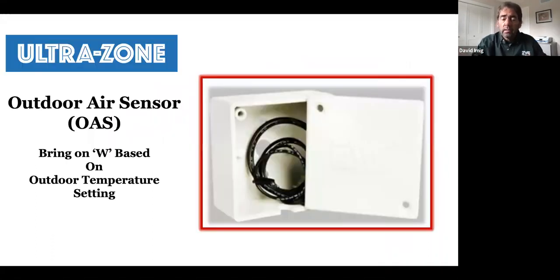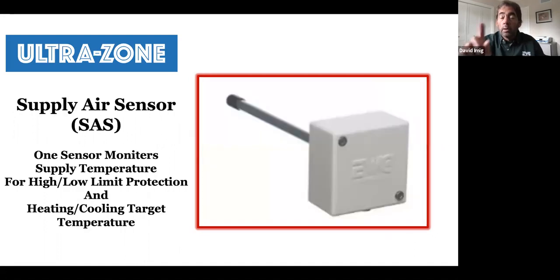Supply air sensor, again, if it's needed, is typical to any outdoor air sensor. I'm going to mount that on the outside, wire it back to my outdoor air sensor terminals. Now, we do give you a probe in that box with that outdoor air sensor.